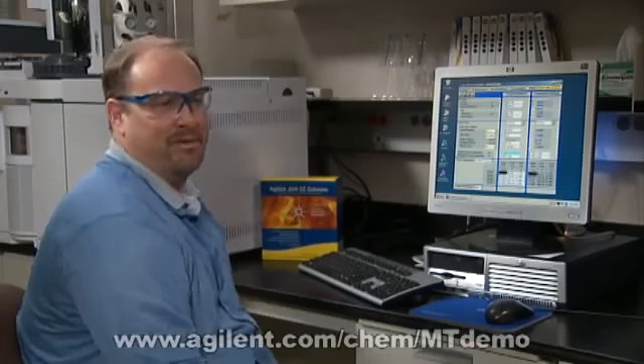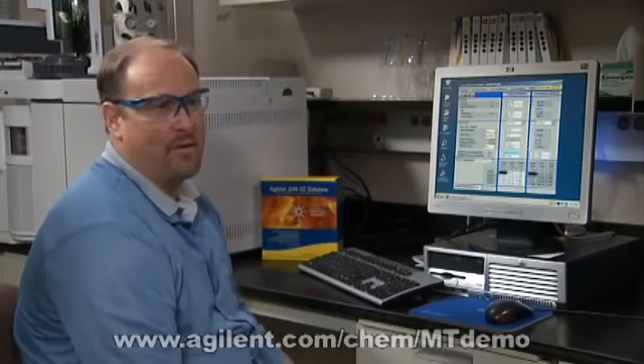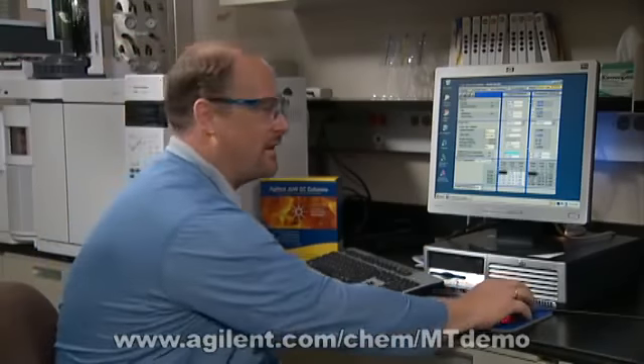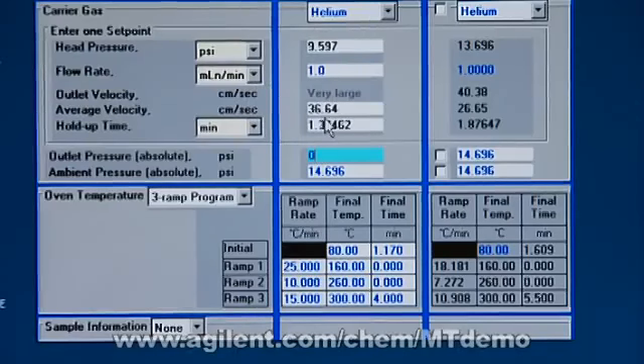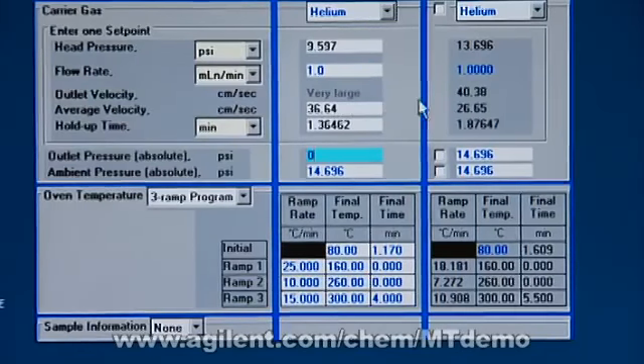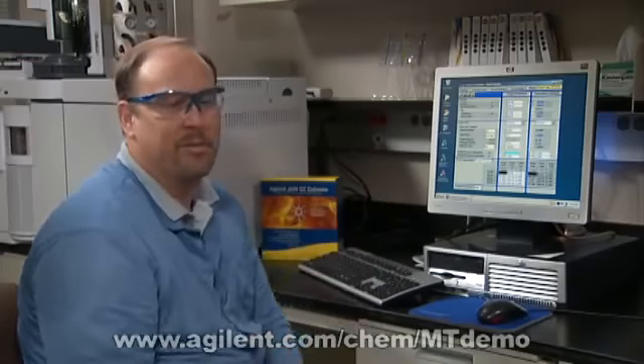It doesn't even give you a number, so the speed, the average velocity of the carrier gas as it goes down the length of the column is faster in the mass spec than it is in the FID, and therefore, I have to compensate with a thermal program, and I have a temperature program that's moving through the column so that things don't get messed up.